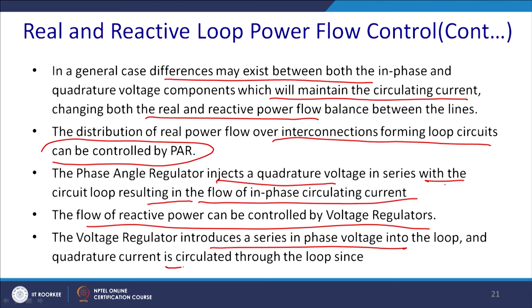Flow of the reactive power can be controlled by the voltage regulator. The voltage regulator introduces a series in phase voltage into the loop and quadrature current is circulated through the loop. Thus, by operating both the PAR and the VAR, we can regulate the power flow between these two lines. Thank you for your attention. I shall continue with our discussions on the phase angle regulator in our next class.